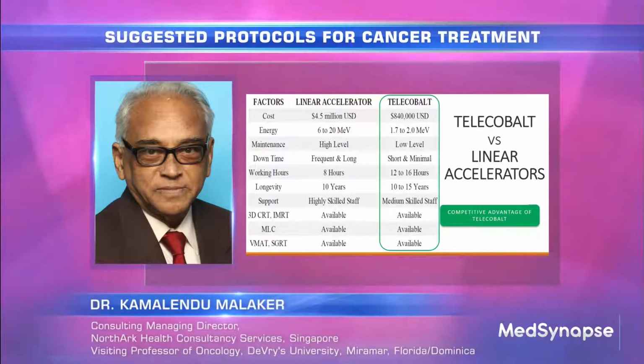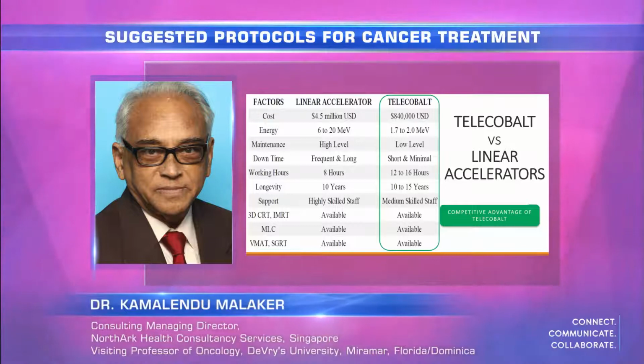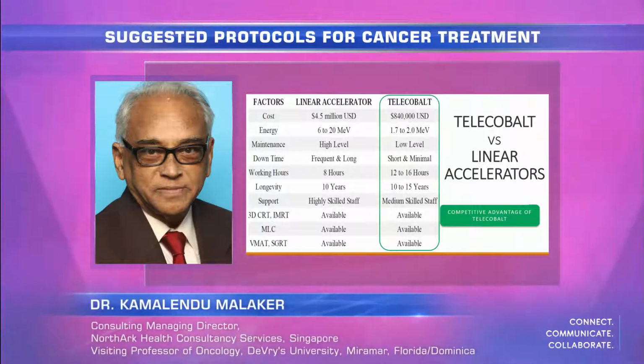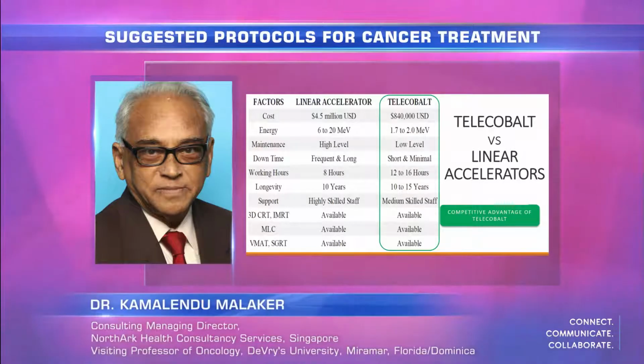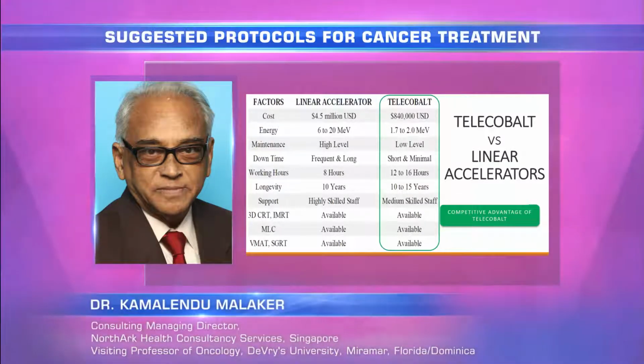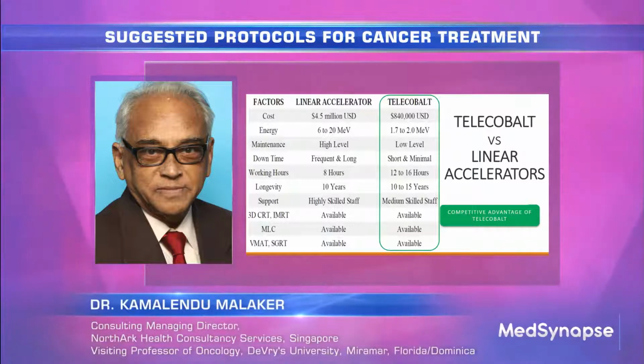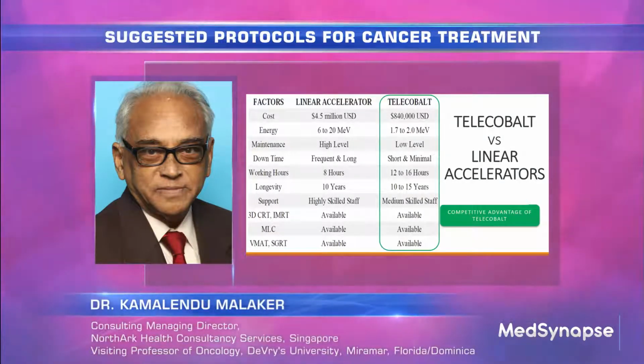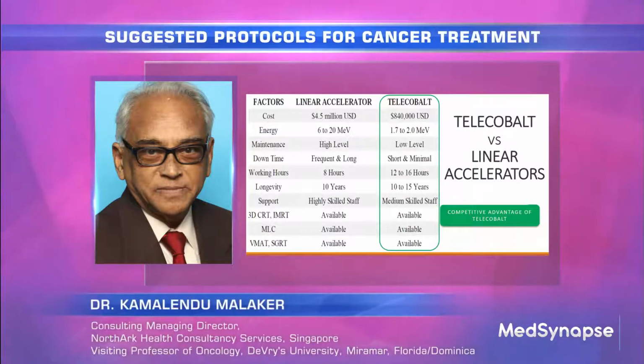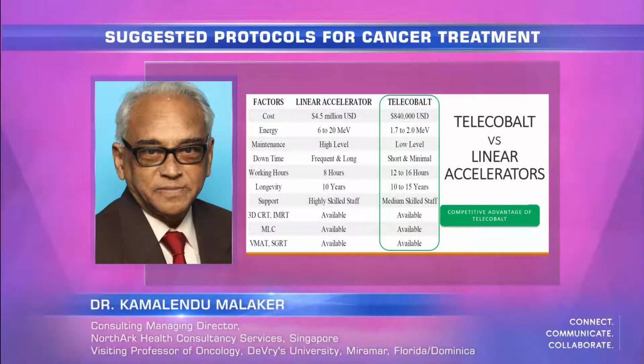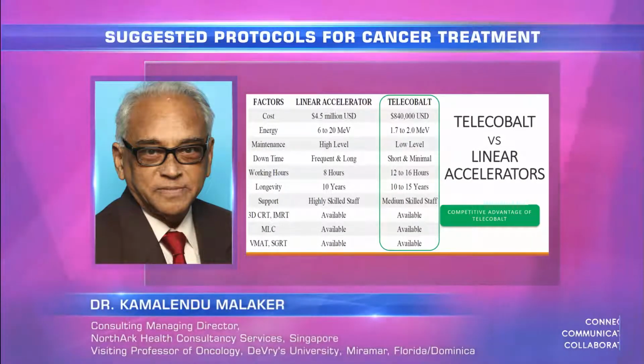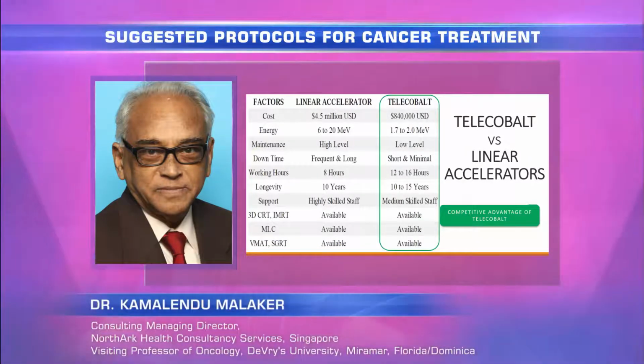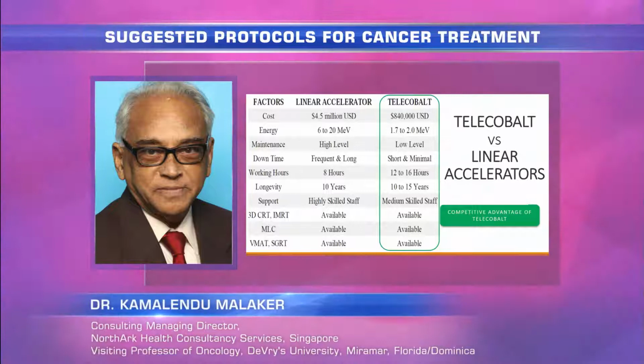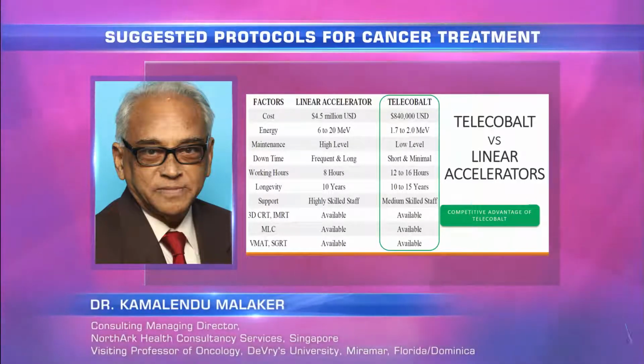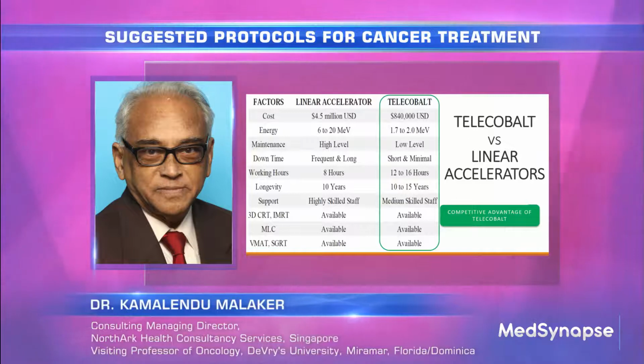The longevity for a linear accelerator is 10 years, and after 10 years we have to change. Now the company tells you that after 10 years you should not be using it. But telecobalt can go on and on for 15 years, providing you change the radioactive source. It lasts for 5 years, 5 to 6, even now 7 years. To maintain the linear accelerator, we need highly skilled staff. But for a telecobalt, we don't need that much. We need skilled staff, no doubt, but medium, the ones who can handle the technology reasonably well.